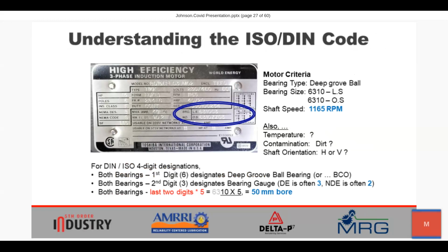Here's another example of that. In this instance, we have 6310 on the load side and the same size bearing on the opposite side. We have the motor speed, 1165. For both bearings, the first digit, 6, designates a deep groove ball bearing. The second digit, 3, designates the gauge of the bearing. The last 2 digits, when multiplied by 5, give us the bore dimension in millimeters.